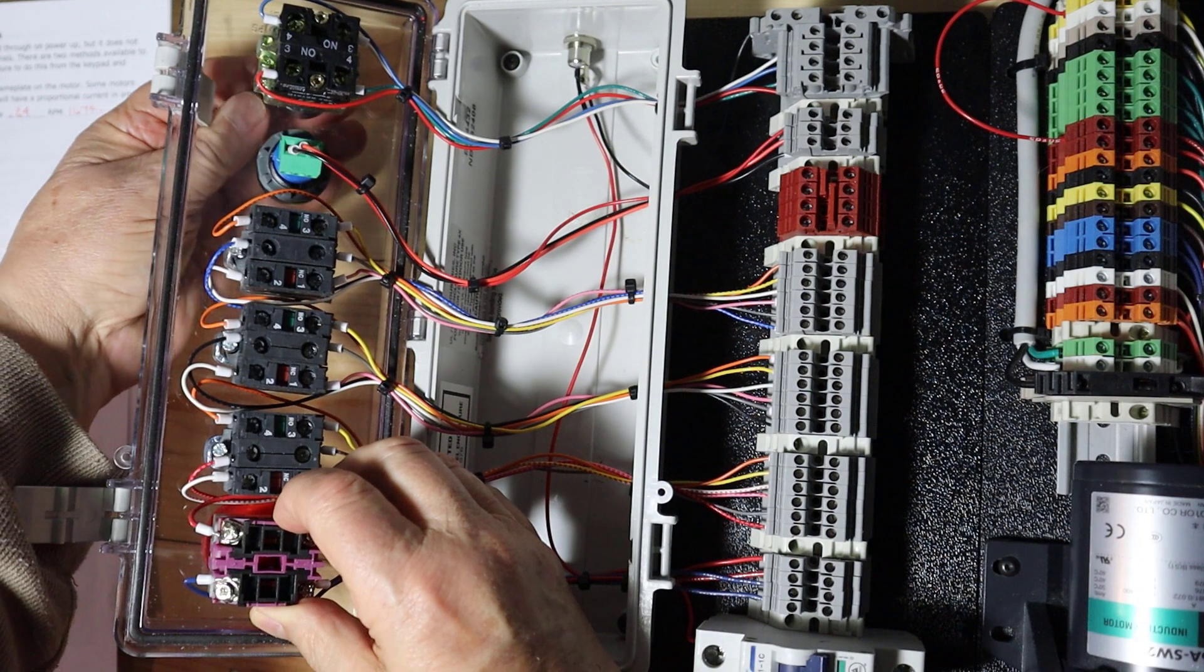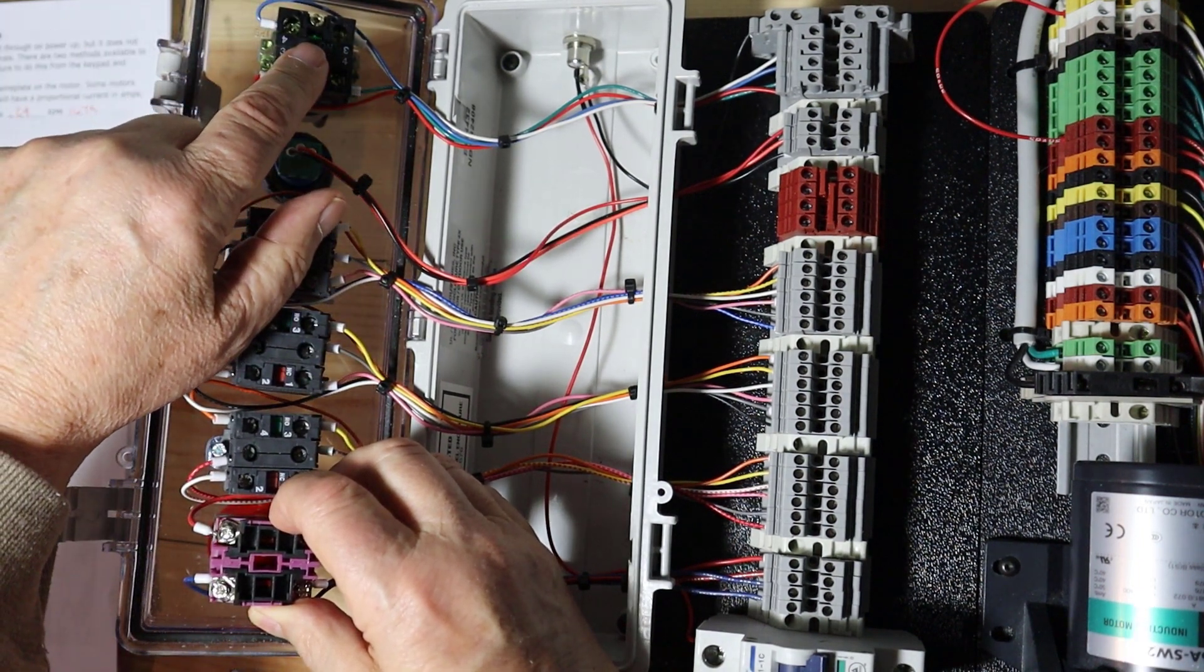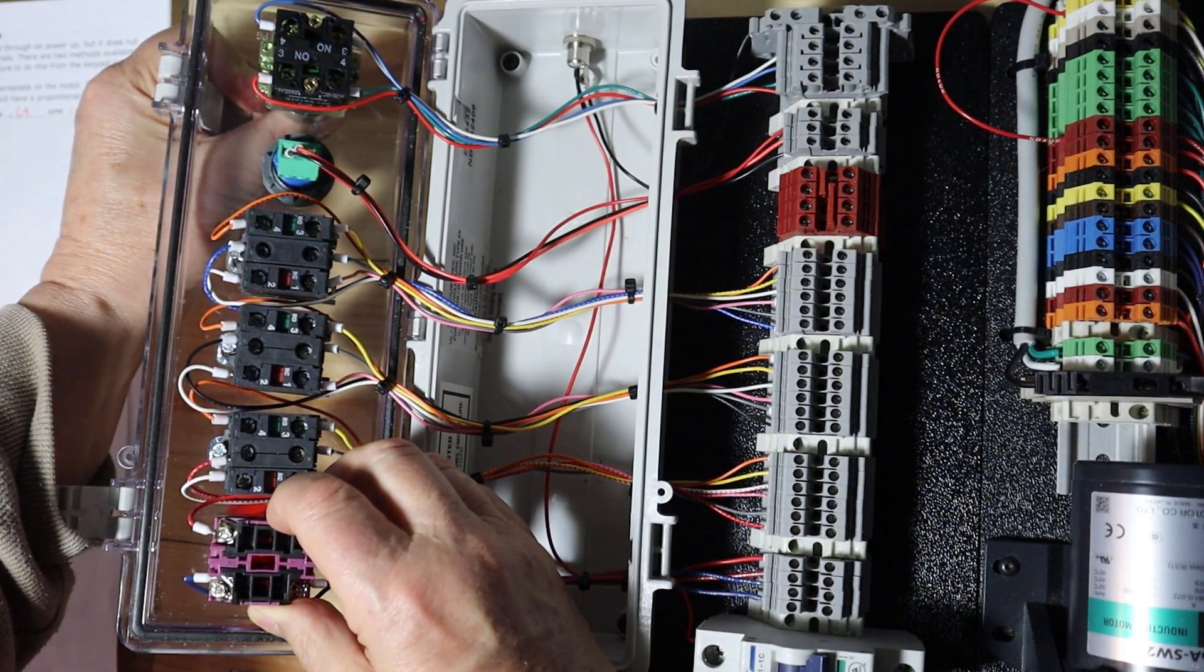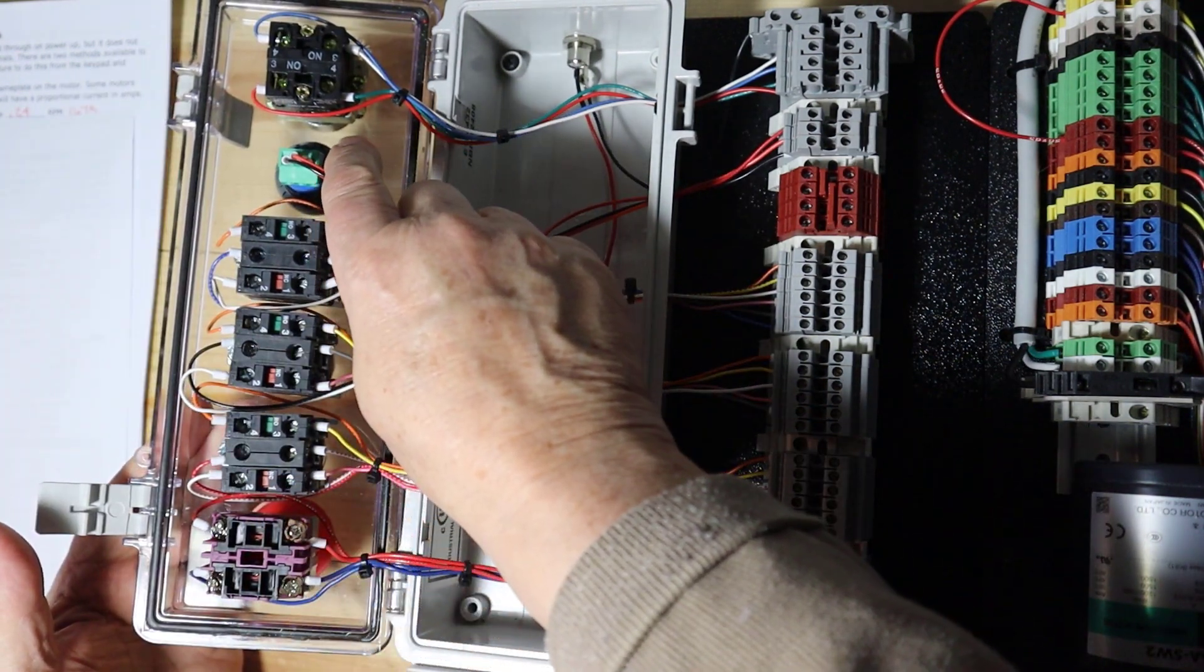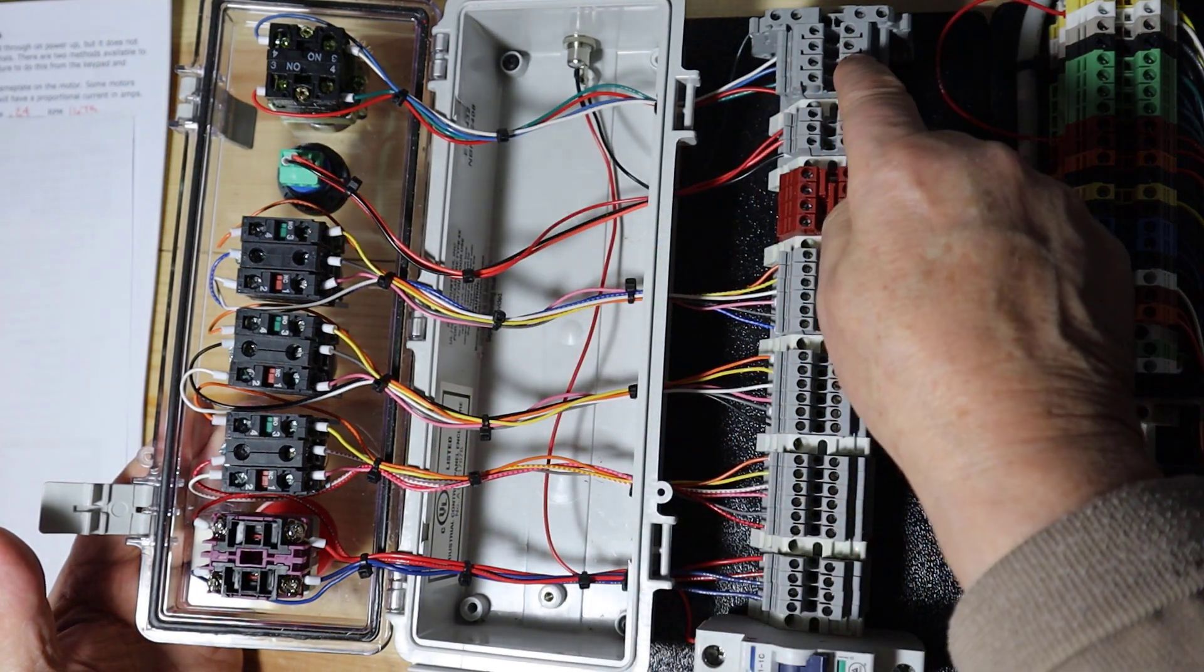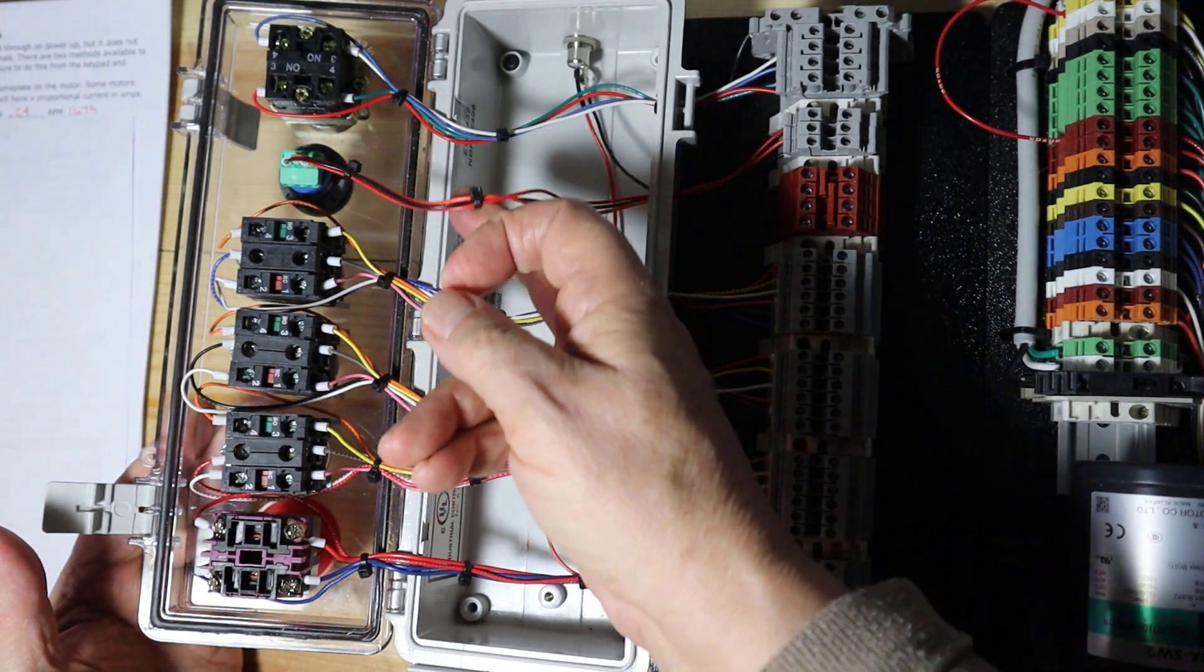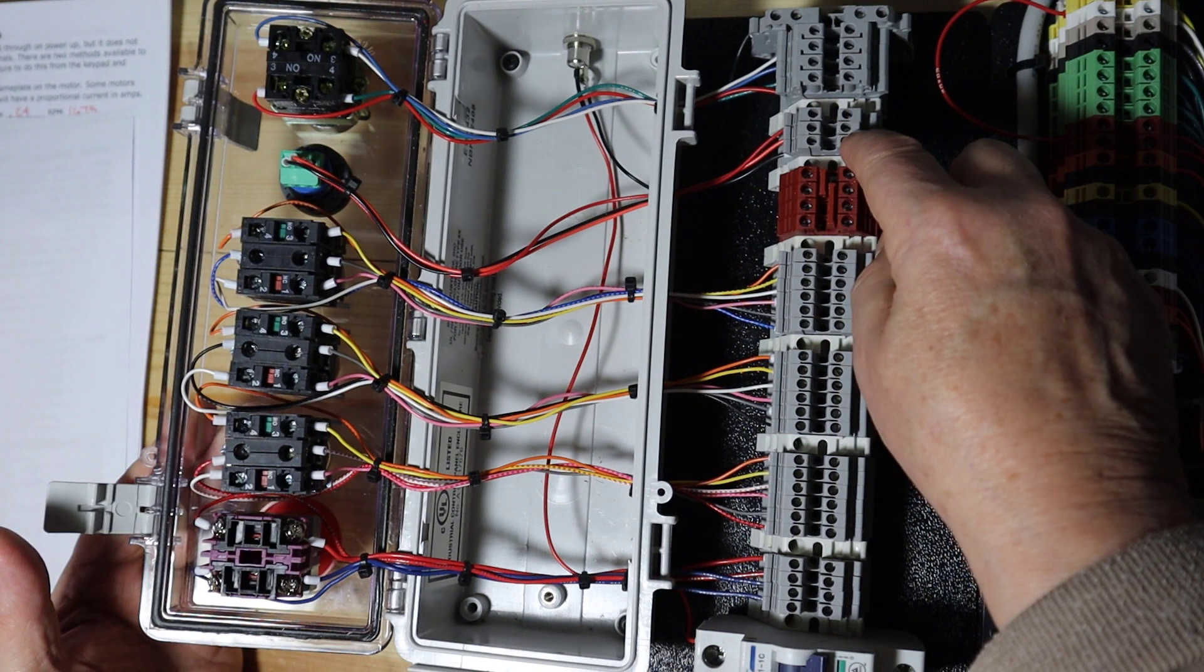If we go to the up position, you saw the green pop up right there. So keep your eye here and here. We go to the other position, you see the green pop up. Now what we've done here is we have four wires running from this selector switch over to this terminal block or set of terminal blocks. We have the three wires from the potentiometer running over to these three terminal blocks.